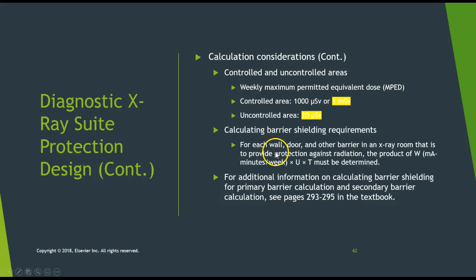Just remember, for each wall, door, and other barrier in an X-ray room that needs to provide protection against radiation, the product of W, remember what the W is used for? That's called the workload. The U is the use factor, and the T makes no sense, but it's the occupancy factor. All of these things go into determining what the barrier lead equivalent needs to consist of.